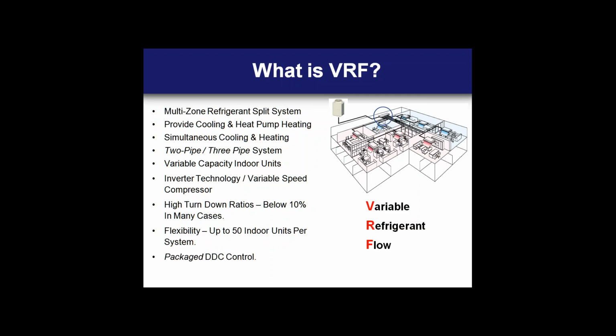With that, the outdoor unit responds to that varying load with a variable speed scroll-driven compressor technology. And with this technology, you'll see high turn-down ratios, below 10% in many cases. There's also a great deal of flexibility.